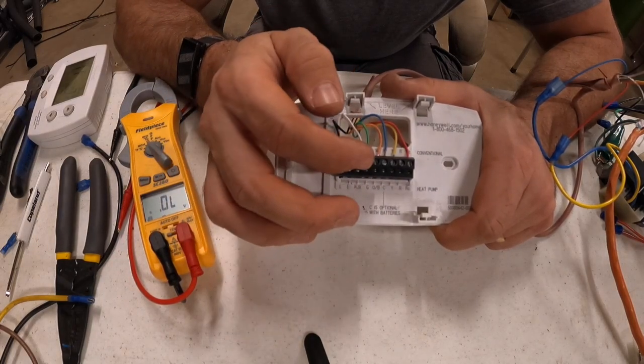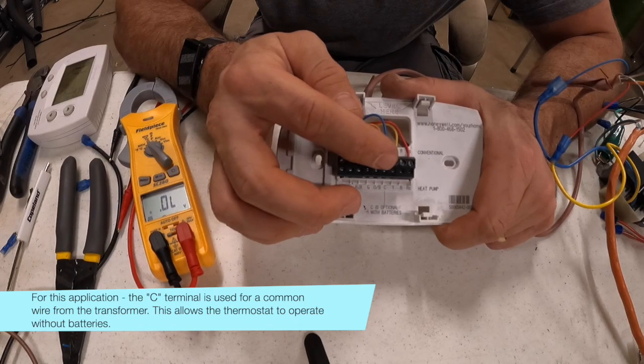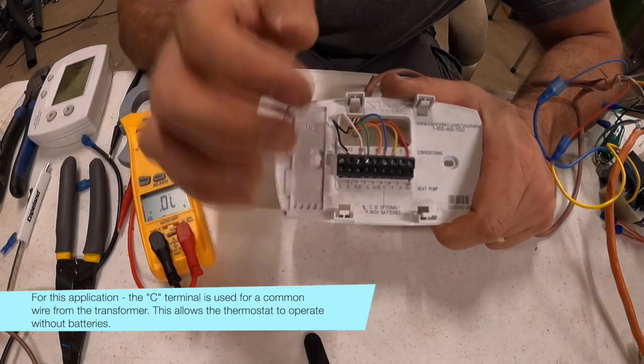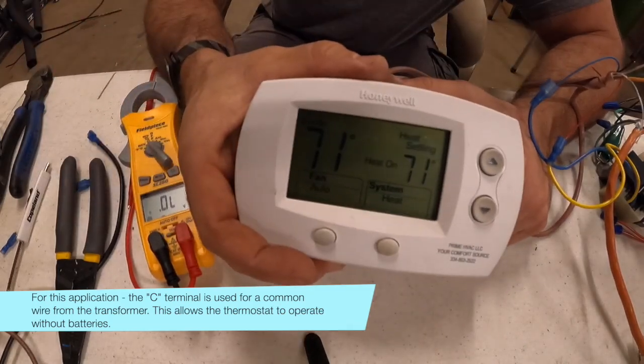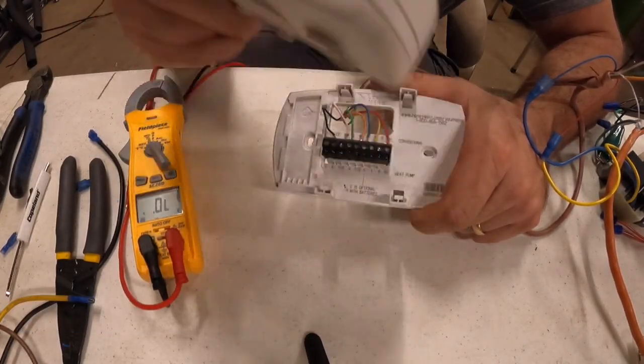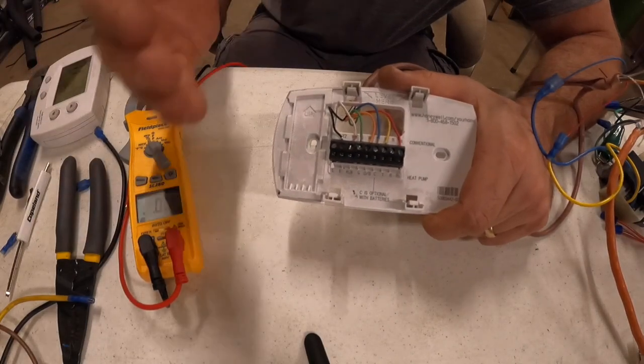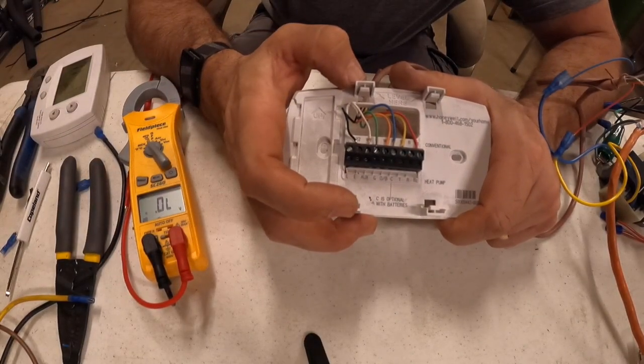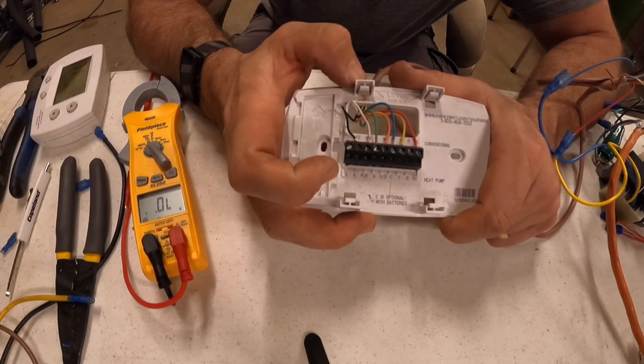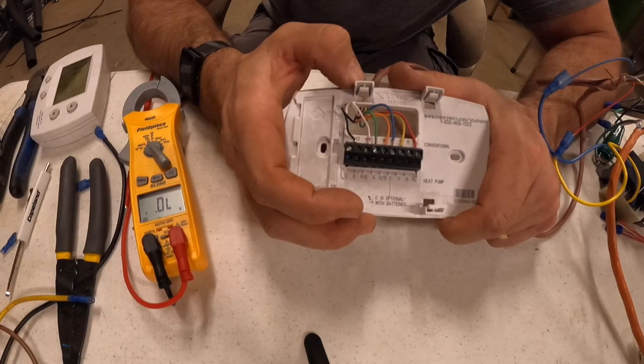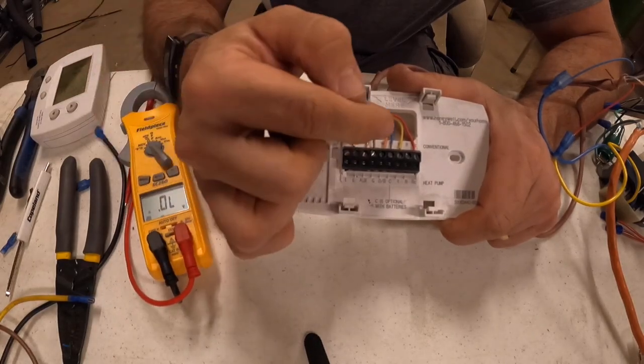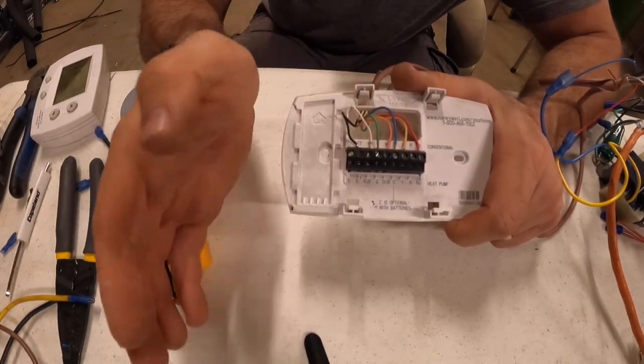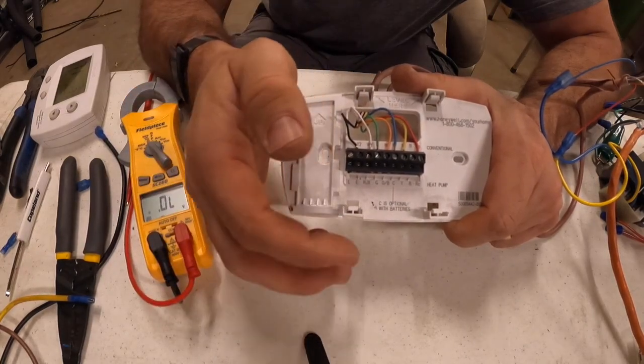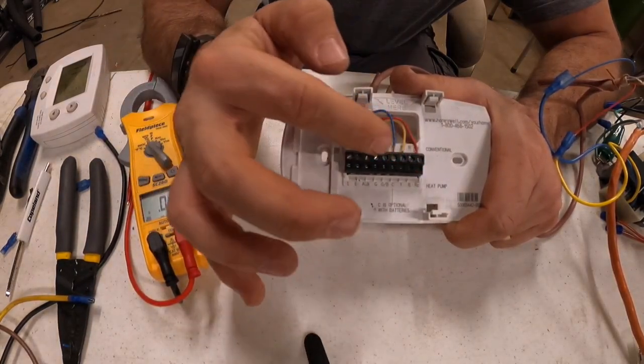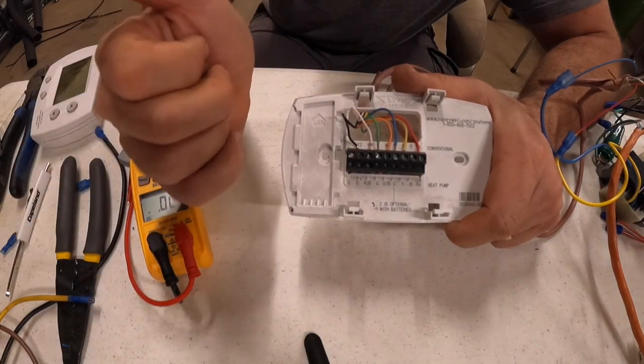C, the only purpose that C serves coming to the thermostat is to power the thermostat. So I've got batteries in this one right now, but you can take these batteries out, being that C is here, and the unit will provide power. We like that setup without the batteries, and we tell our customers that if the thermostat ever goes blank, that means there's a problem. Putting batteries in it will not make the unit work. So that is the only purpose C serves. C isn't designated to any terminals. It is only here to close that power supply to the thermostat.